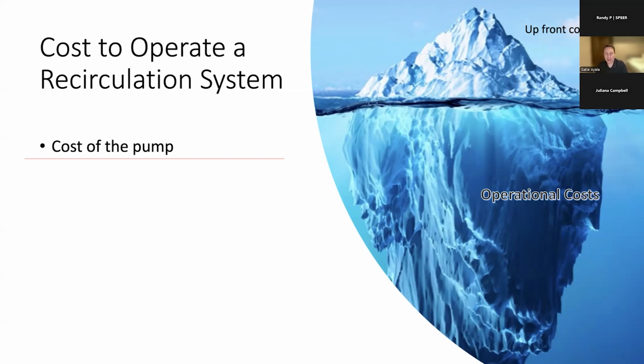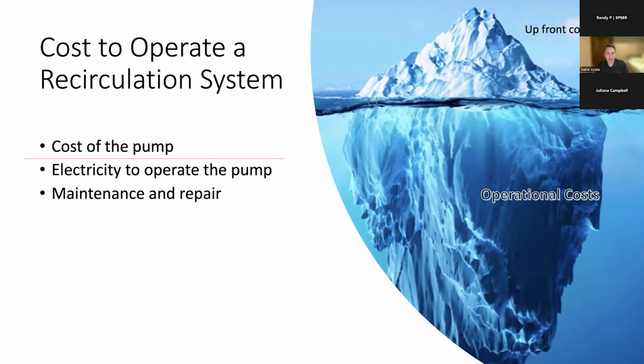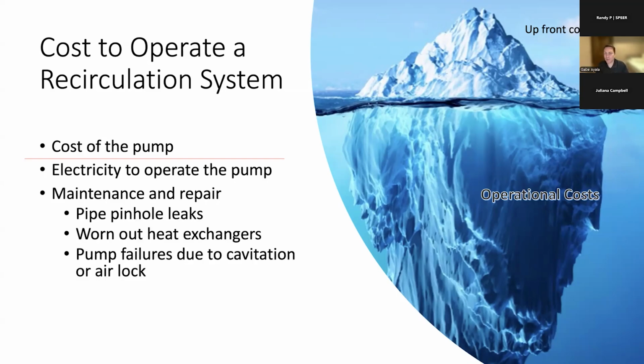Running a recirculation pump by itself is not inherently energy intensive. It's a small fractional horsepower pump, but you do have the electricity to run that pump, right? So if you're running the pump excessively, you are going to be consuming some kilowatt hours from that pump. There's also the non-energy costs, the maintenance and repair. Hot water recirculation can be very damaging to a plumbing system if left uncontrolled. Pinhole leaks, scaling in the heat exchanger of a tankless water heater, worn out heat exchangers, all of these things contribute to operational costs. And then there's this one, heat losses through distribution.